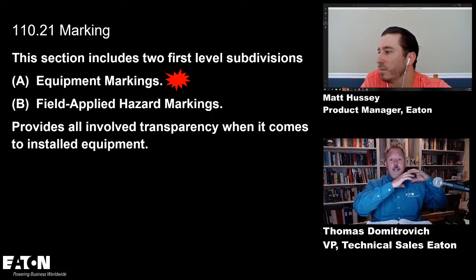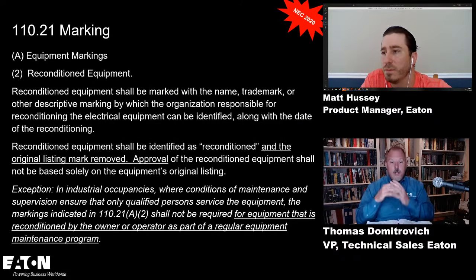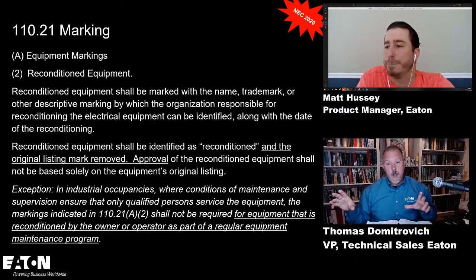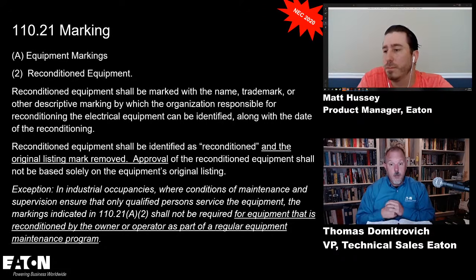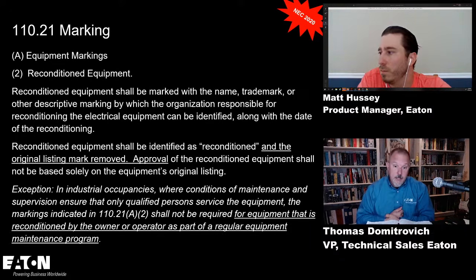What else? The section includes 2 first-level subdivisions, equipment markings. Now, once you define that what you're doing is reconditioning, then the 110.21(A) marking requirements tell you that you've got to remove the original listing mark. You have to put your name on that equipment, that you are now the owner of the reconditioned equipment. You're now the new responsible party, basically. And then they put in the exception for equipment that is reconditioned by the owner or operator as part of a regular equipment maintenance program.